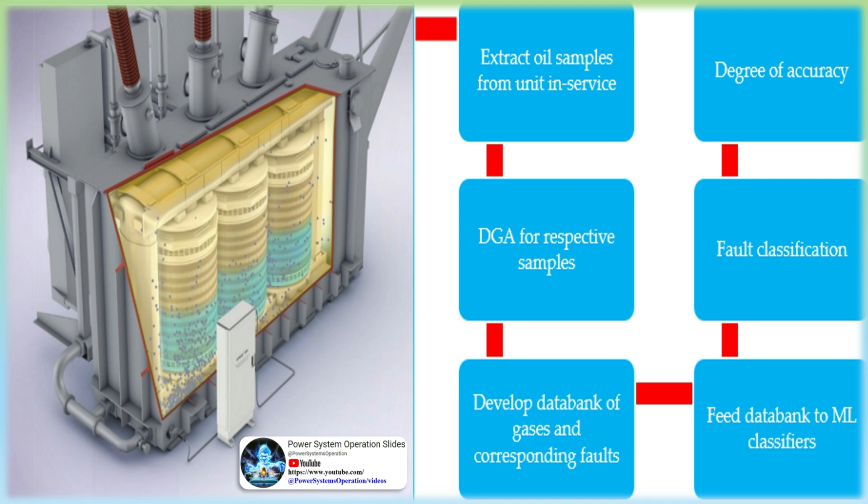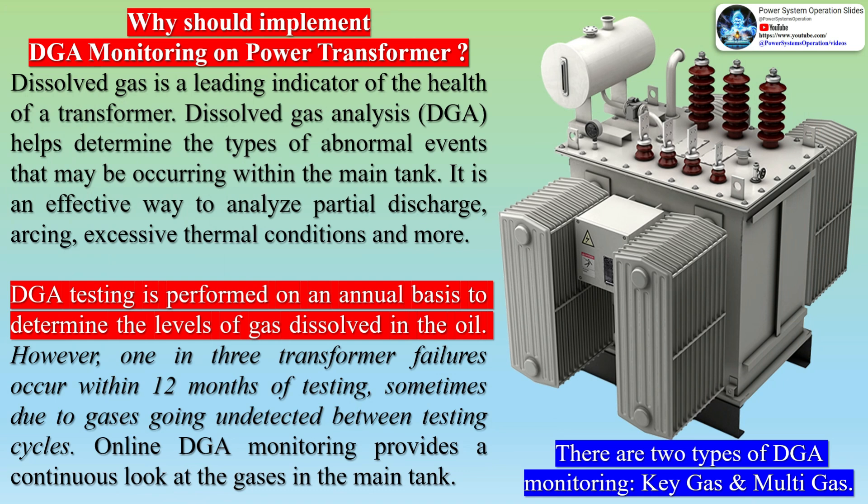DGA testing is performed on an annual basis to determine the levels of gas dissolved in the oil. However, 1 in 3 transformer failures occur within 12 months of testing, sometimes due to gases going undetected between testing cycles. Online DGA monitoring provides a continuous look at the gases in the main tank.